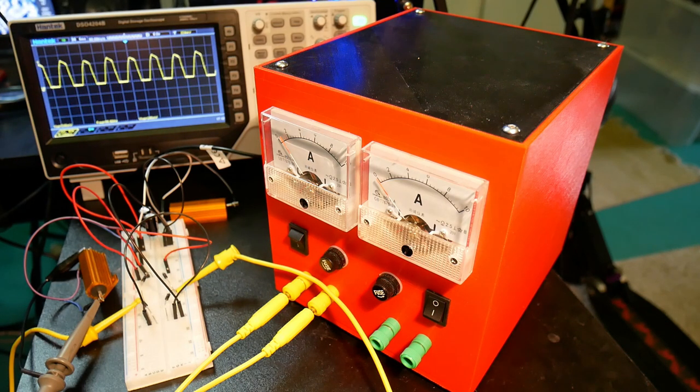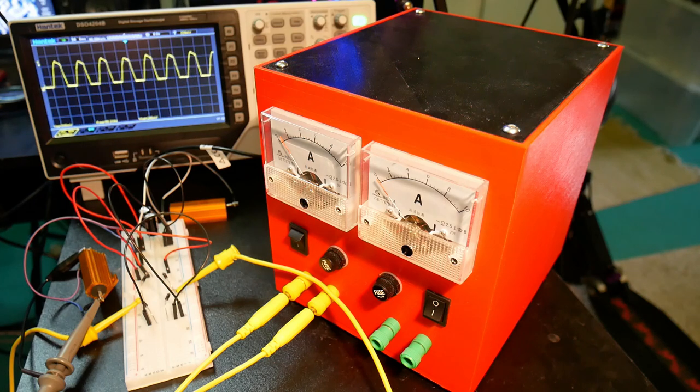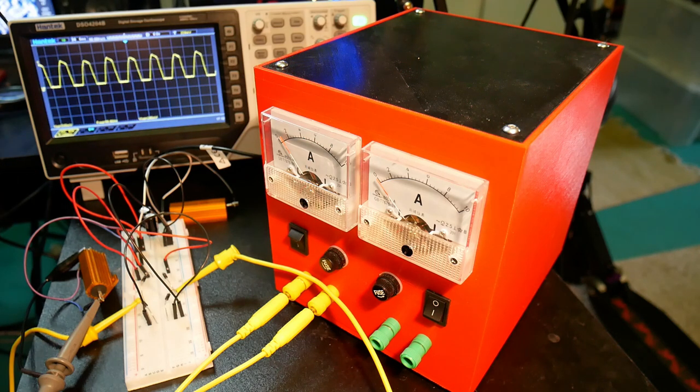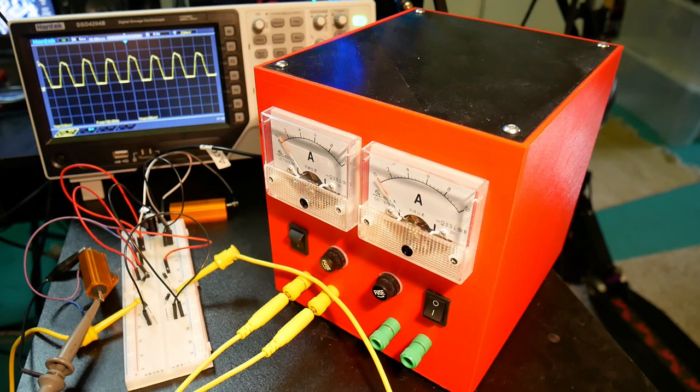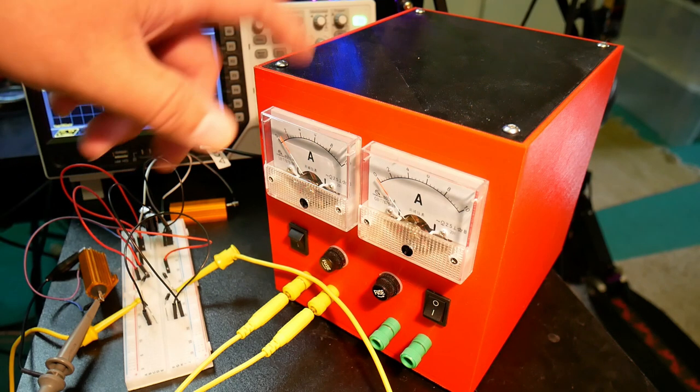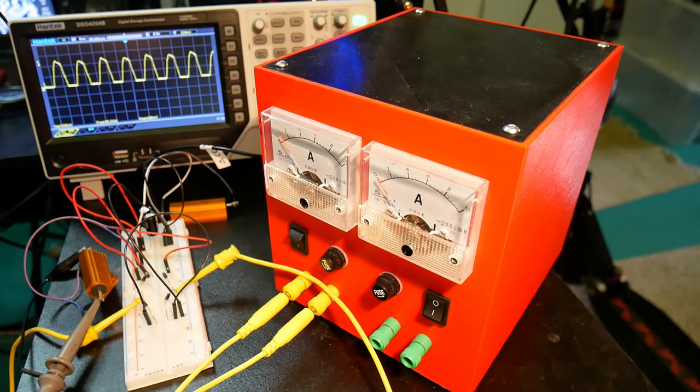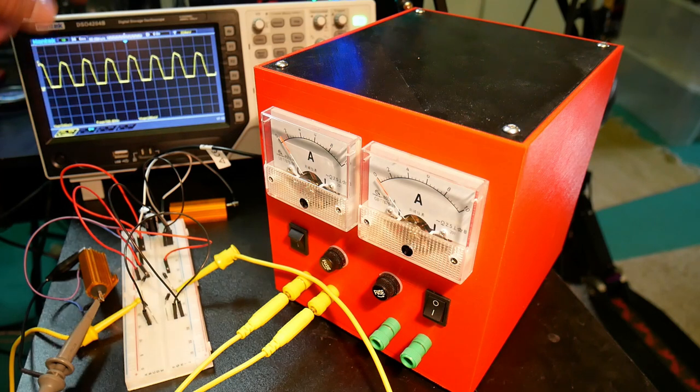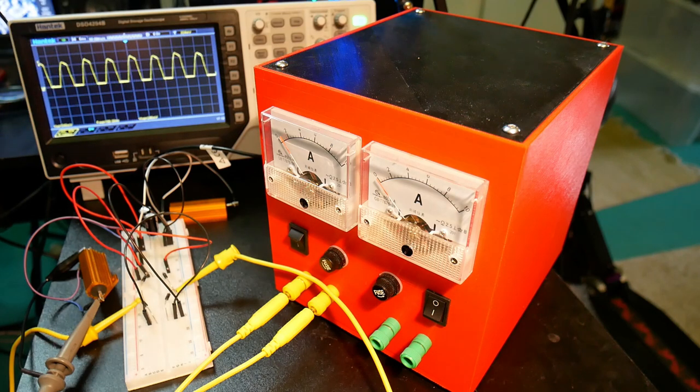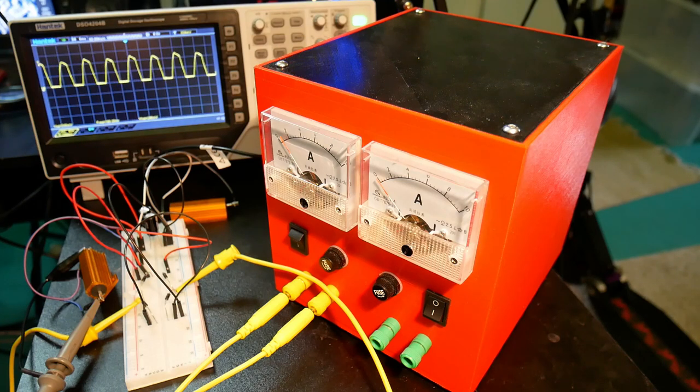And this is the effect of, basically, the side effect of trying to reduce the ripple just by using capacitors, is that you actually, unknowingly, you actually increase the thermal load on the transformer. Because this spikey use of current will actually induce thermal load on the transformer.